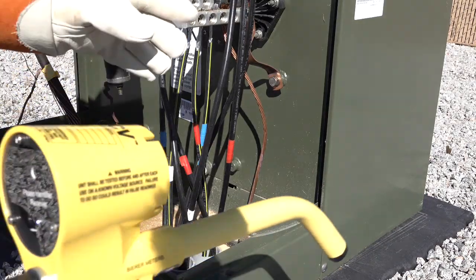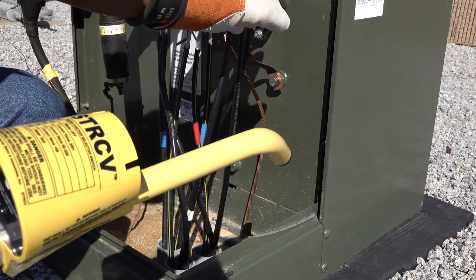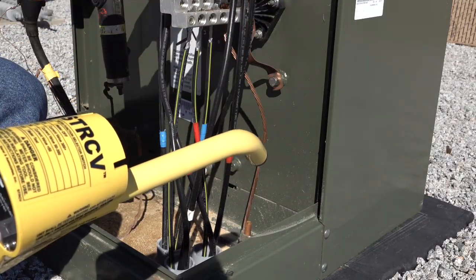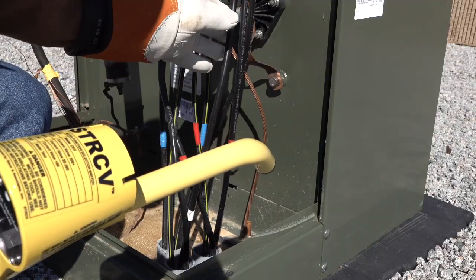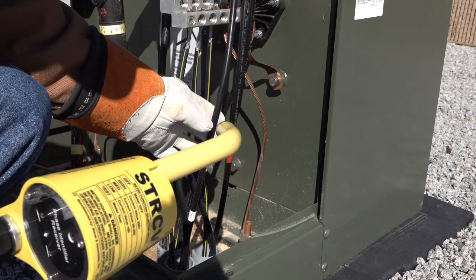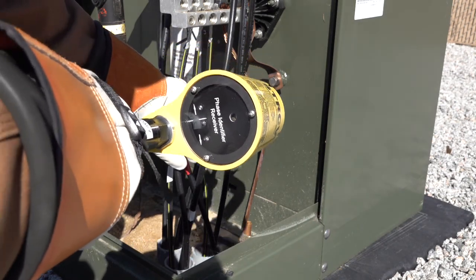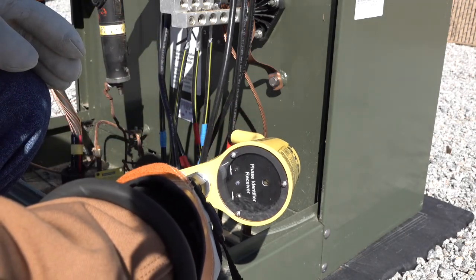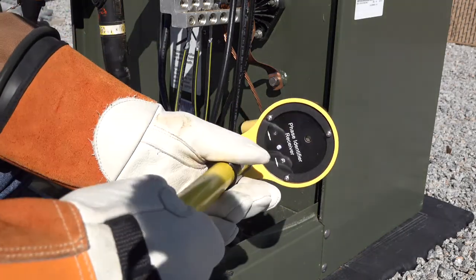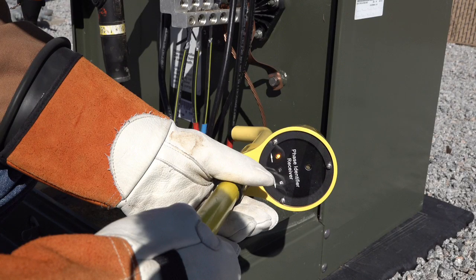With the ST800 still pulsing 800 amps and the STRCV still in a high switch position, we want to afford ourselves the most room possible. To get the most reliable, consistent reading, place the concave STRCV cone tip perpendicular to the conductor, and also as far away as possible from the other conductors. Notice the lit LED and the corresponding arrow. The arrow is pointing up into the transformer and away from the ST800.